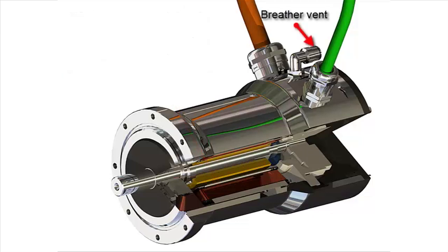A breather vent is also provided as a standard feature. During washdown, pressure differentiation can cause a vacuum effect that can suck moisture into the motor housing. Our breather vent allows the user to run a hose to a dry air location to prevent this common cause of failure.